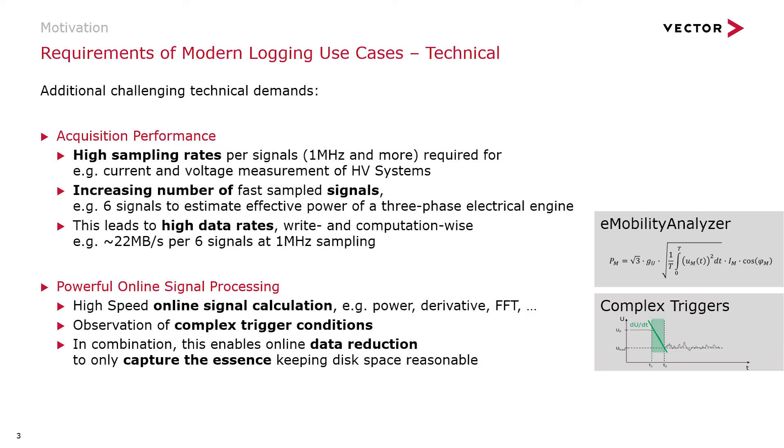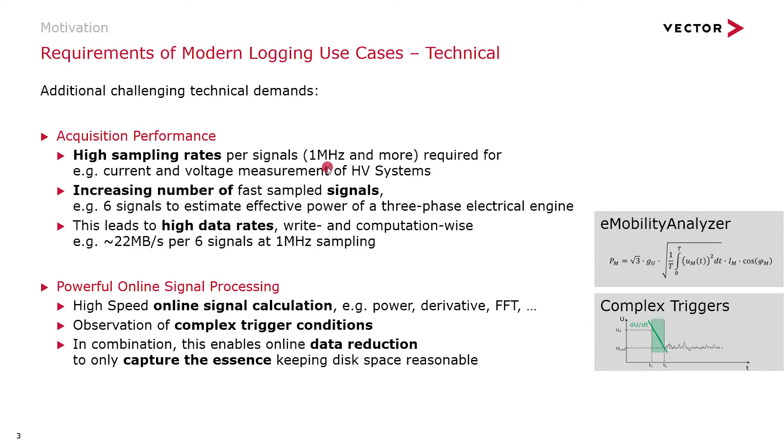Modern logging applications also demand high performance recording of data. If you think of testing an electrical drive, you would have to measure the voltage and currents to your electrical motor, which is typically a three-phase motor. So you have three times the voltage and three times the current that you would have to measure. The voltage is typically modulated as a PWM signal at about 20 kHz. With an oversampling of at least 10 or even more, you could say 1 MHz sampling would be sufficient for all six channels. But already these few signals, just six signals, result in a data rate to hard disk of about 22 MB per second. In a 10-hour shift, this is about 800 GB that your logging system has to be capable to record.